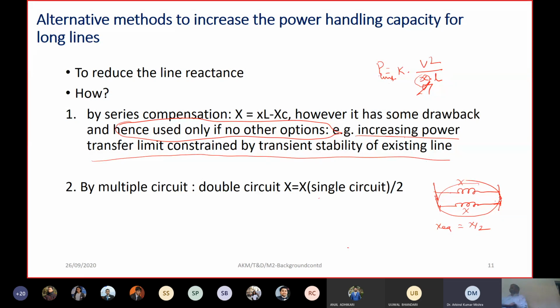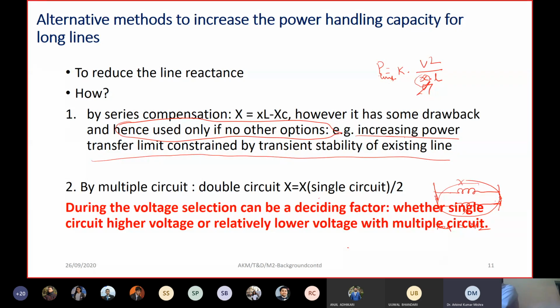So another method for increasing the power transfer capability can be improved either by going for higher voltage during the design, or by going for multiple circuits. So during the design, the voltage selection, whether to go for a single circuit at higher voltage or a relatively lower voltage with multiple circuits, is also a choice for the designer.